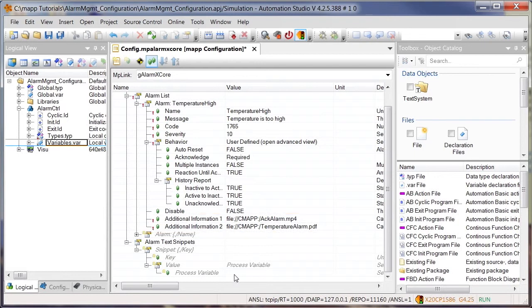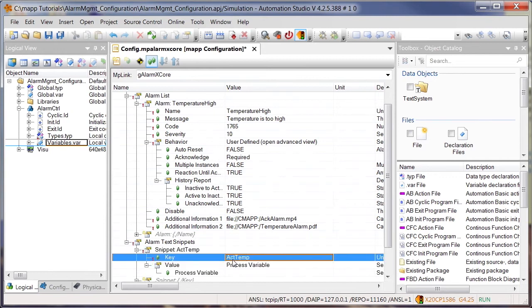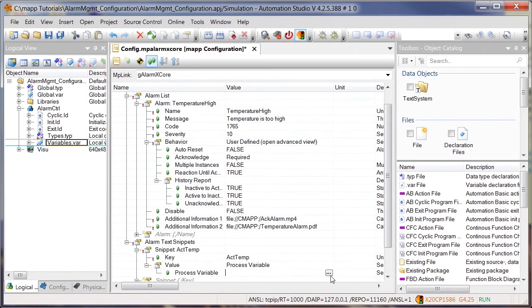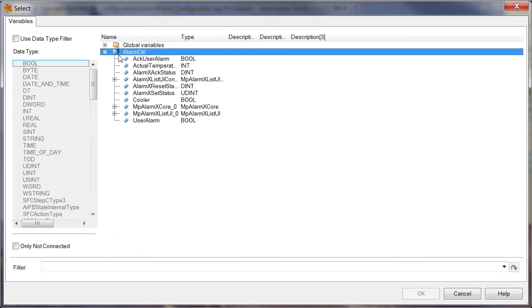To integrate application data in the alarm text, we use text snippets. If a temperature alarm is triggered, for example, the current temperature value can be included in the alarm text by creating a text snippet. First, you need to specify a key that will be used later to identify the text snippet in the text. Then you select the variable in the application that contains the current temperature.